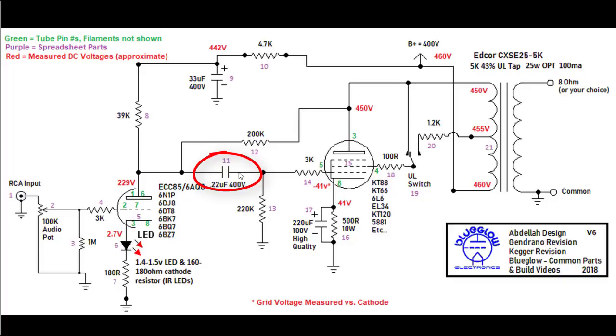If you're trying to figure out whether your coupling capacitors are leaking, measure the voltage on one side with your black lead to ground and red lead on the multimeter. Say you get 229 volts there. Now read the DC voltage on the other side of the capacitor. If you get 10, 50, or 100 volts there, your capacitors are old, dried out, and leaking, and need replacing. But if you read 0 volts or close to it, they're in good shape.